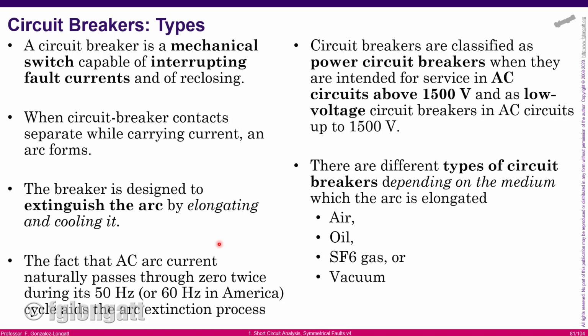What I want you to understand is that circuit breakers can be classified in many ways. However, it's important that you understand that low voltage circuit breakers are very different from high voltage circuit breakers. And we say here low voltage circuit breakers are everything below 1500 volts. That is what the standards say. And if you go above, it is high voltage.